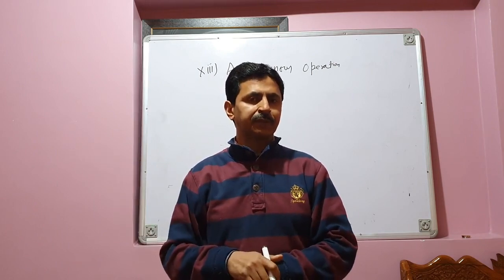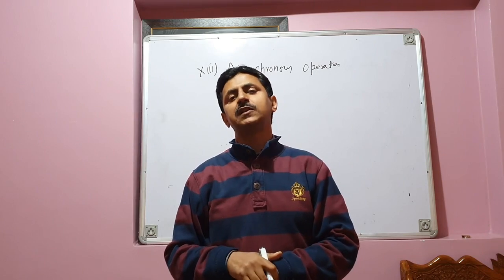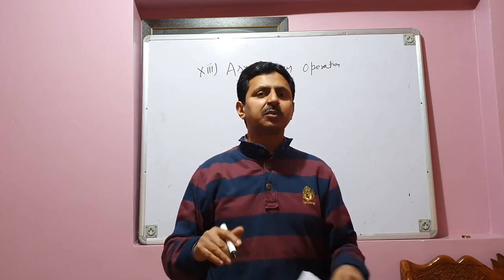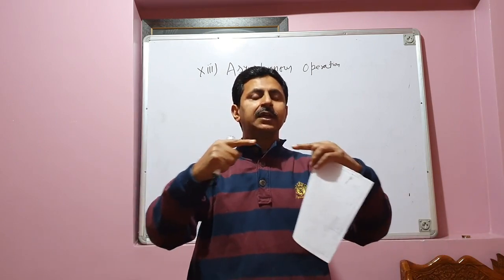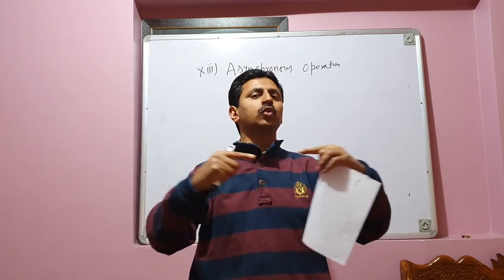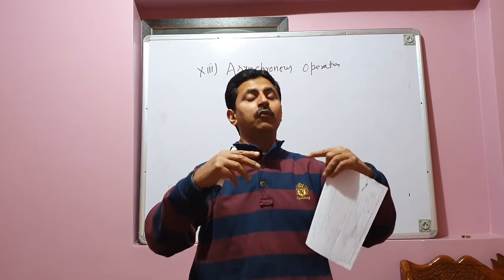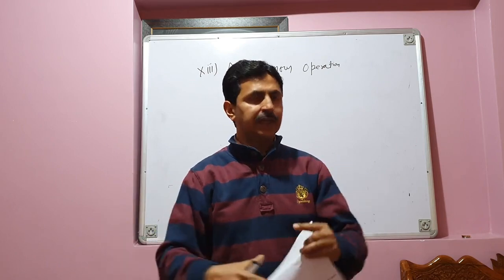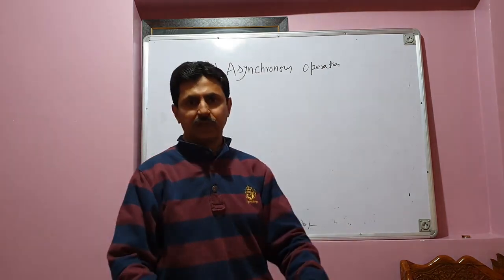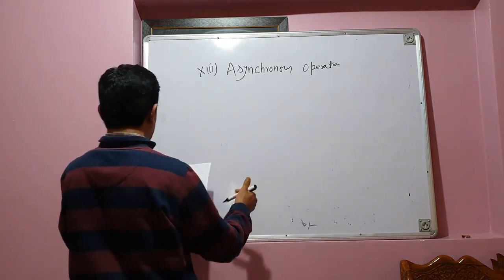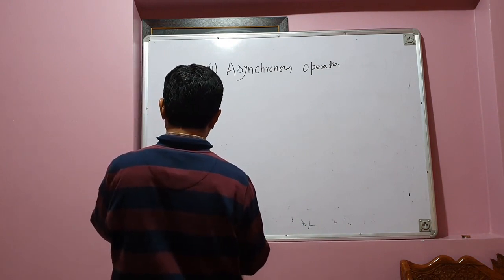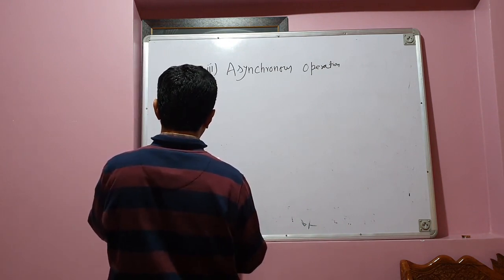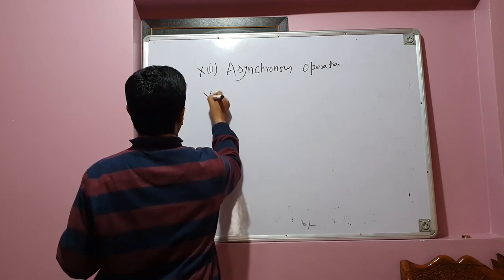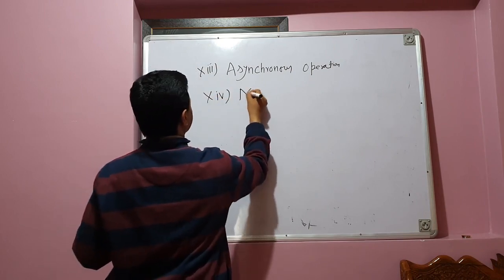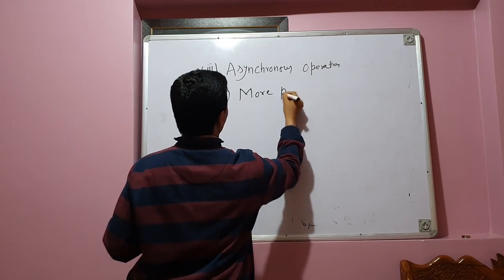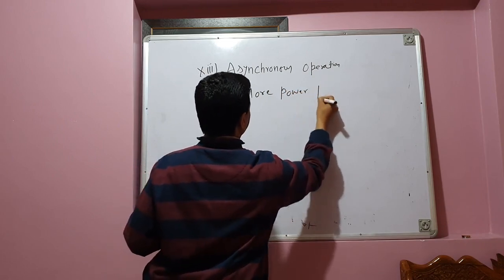So therefore, with the help of HVDC power transmission system, it is possible for us to synchronize two lines or more than two systems which are operating at different frequencies. This is called asynchronous operation. So this is the next advantage of HVDC power transmission system. Next is more power per conductor.